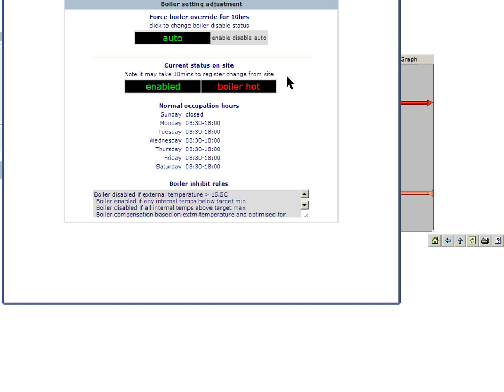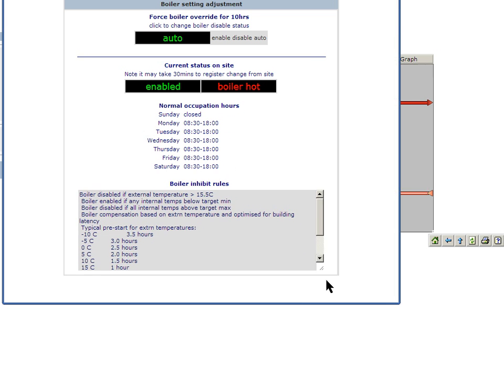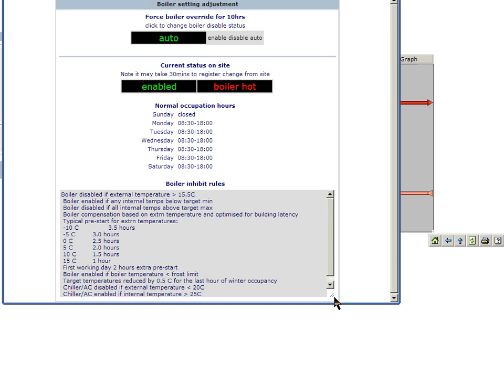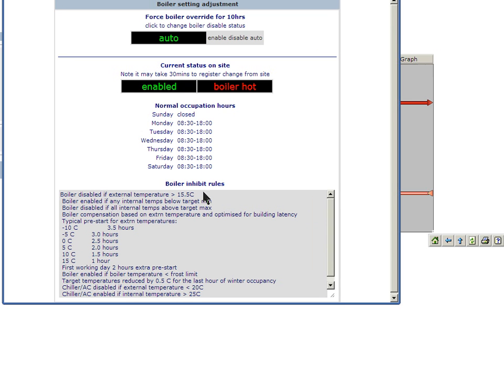Below this is where the site-specific duty times would be set, and below this is where the plant inhibit rules preside. These assure heating and cooling contention are controlled, this often being the area associated with the most waste within a system, where the heating and cooling run at the same time. Providing a dead zone to inhibit this waste can reduce significant levels of consumption. It is also where frost protection and optimized stop and start parameters would be set.